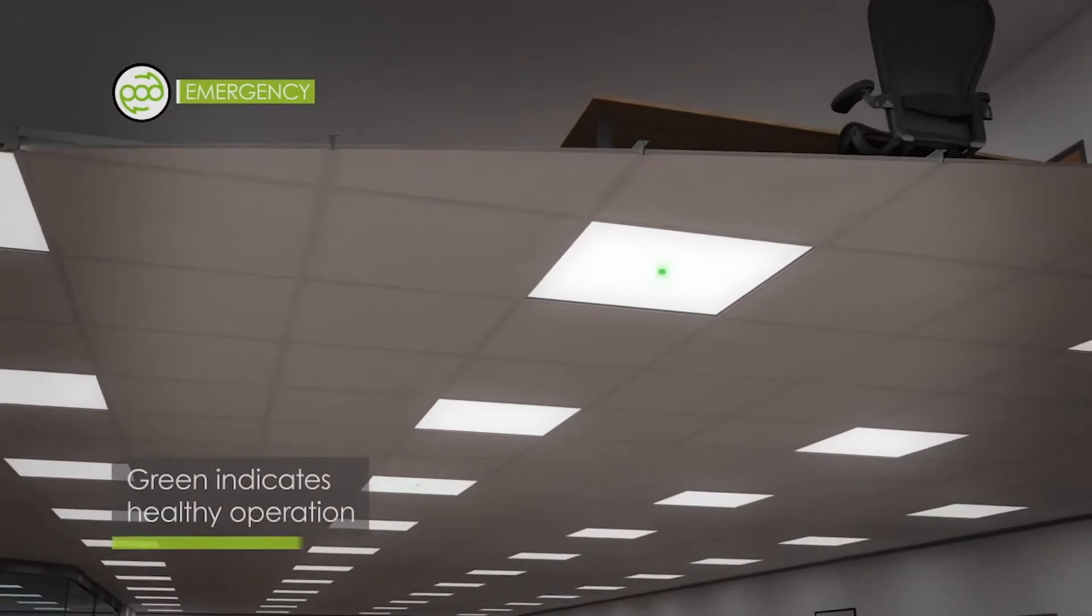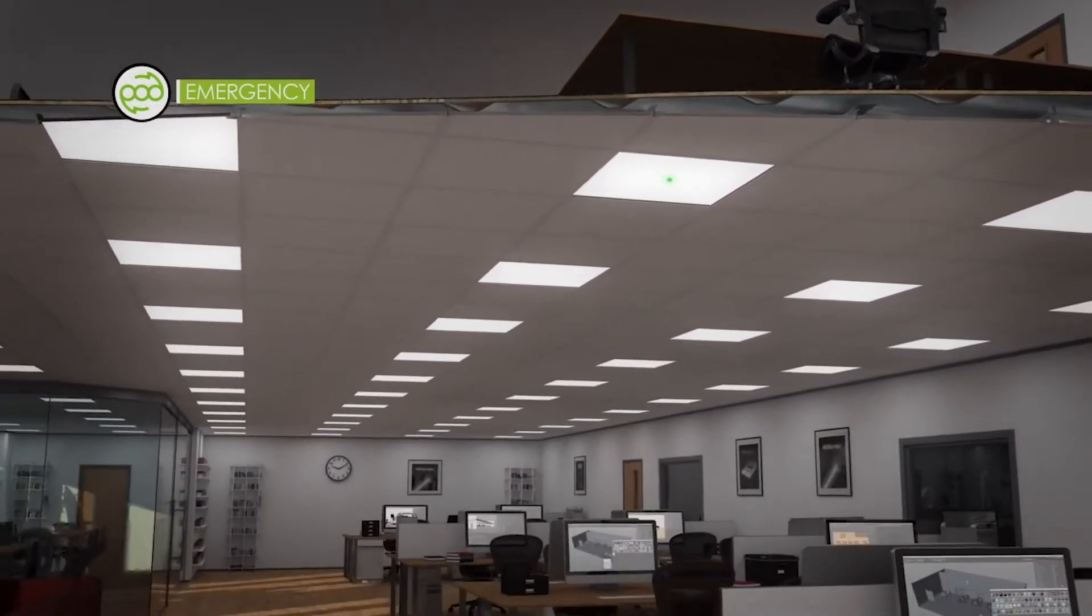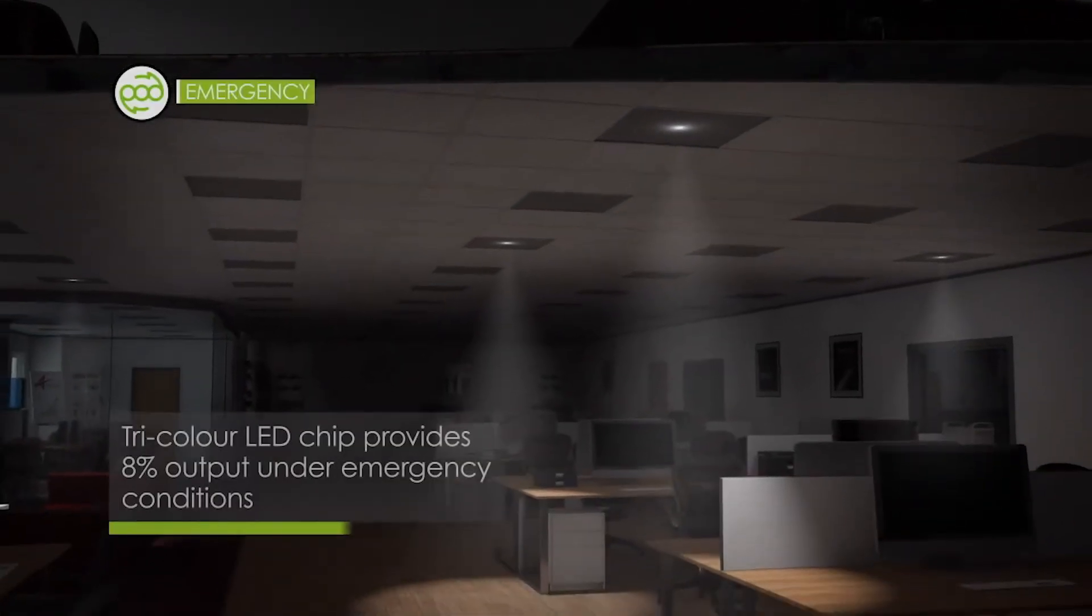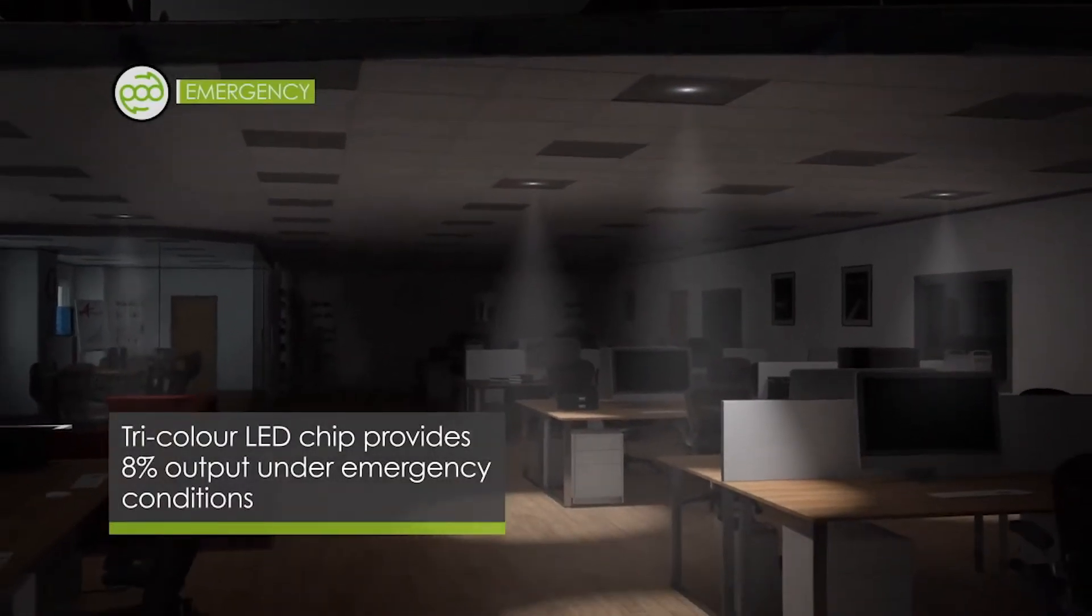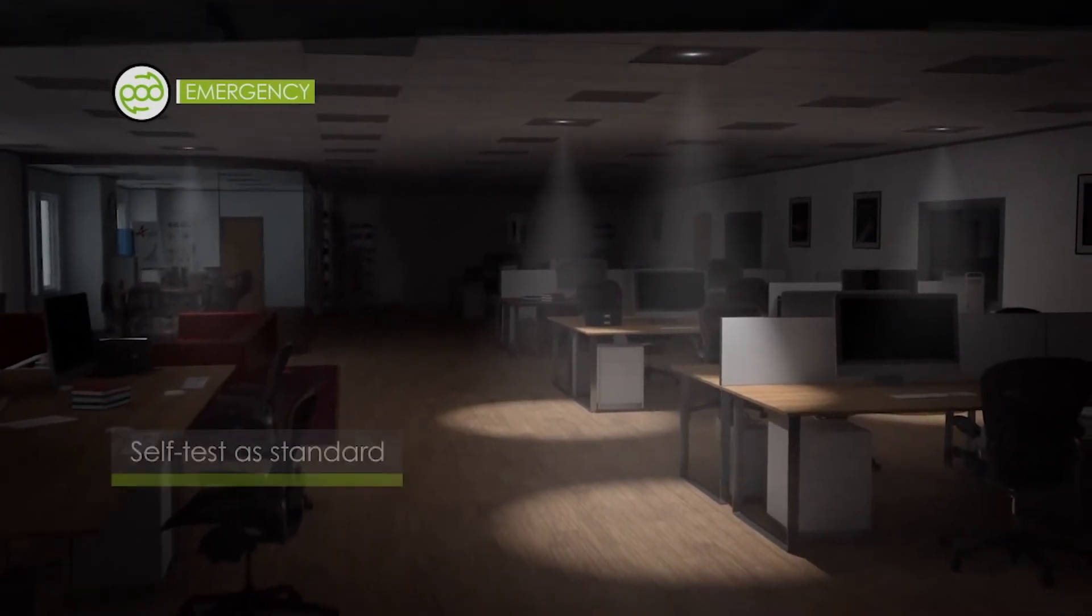This self-test PanelPod emergency has a three-hour non-maintained emergency illumination in power failure conditions. The tri-color LED chip provides our 30-watt panel with eight percent emergency output when the emergency function is activated.